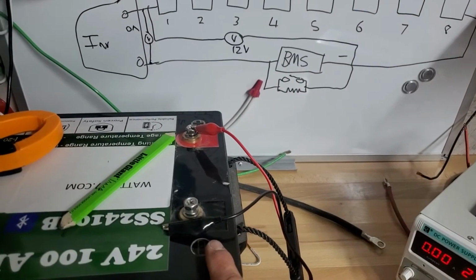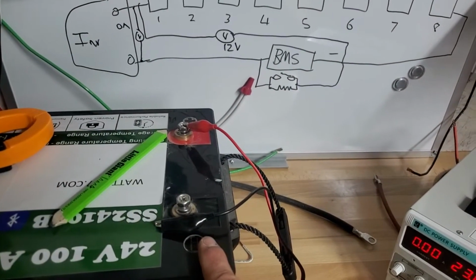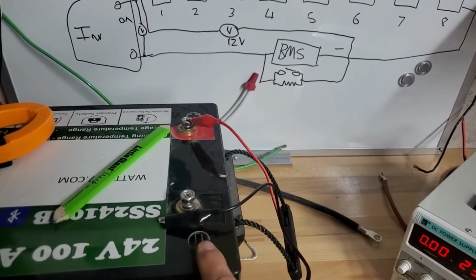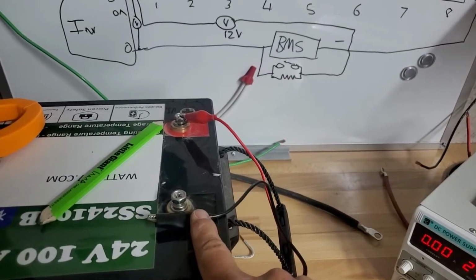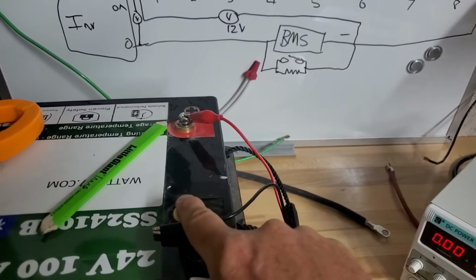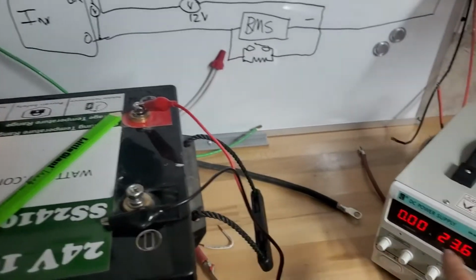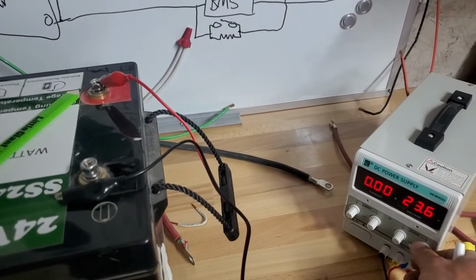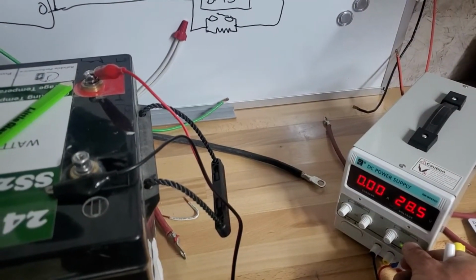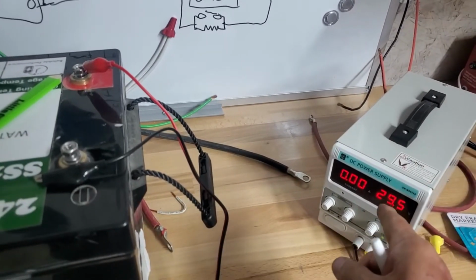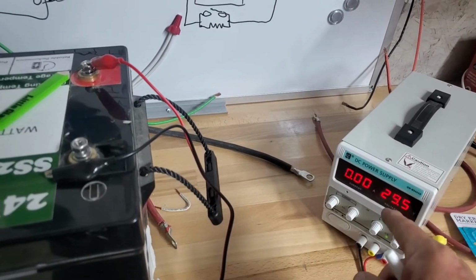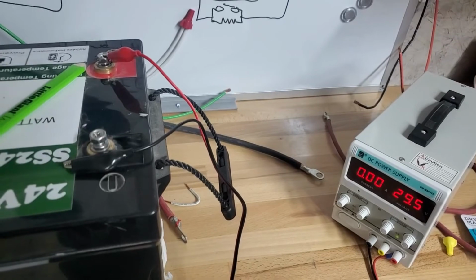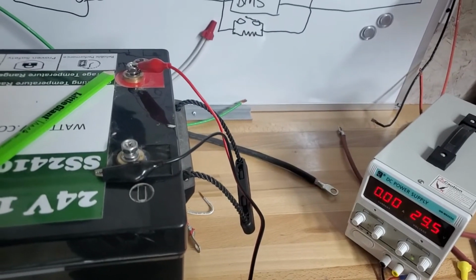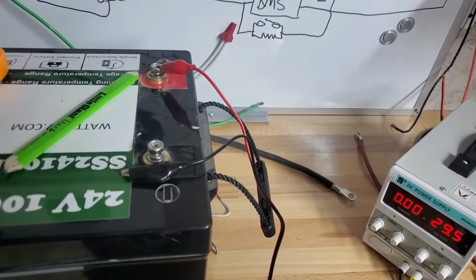Many people ask me, well, the inverter is faulty, it won't charge my battery. I tell them, no, what's happening is your battery is tripping, and the inverter has gone into fault because it pushed the voltage up internally. The inverter battery voltage spikes because it's charging an open circuit battery, throws a fault, and then won't reset itself because there's a problem.